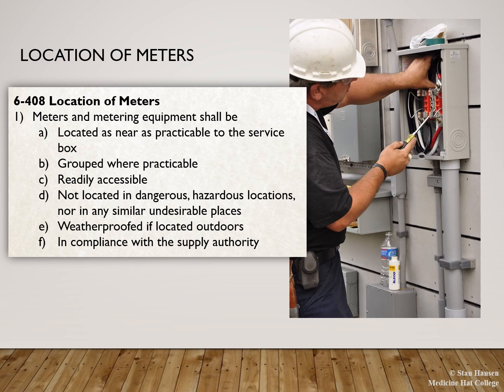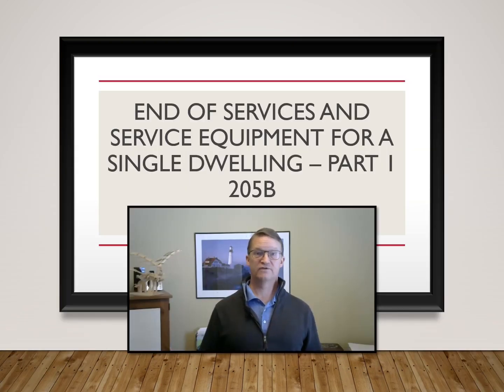When we're thinking about accessibility, we also have to remember Rule 2308, which states that we have to have at least a minimum of 1 meter in front of any of our electrical equipment, and this does include our meter bases. We have to make sure that anybody who's checking on the meter base or working on the meter base has enough level, secure footing to work on it safely. So we can make sure that it's not behind any buildings or structures that's going to impede on that 1 meter rule. So that's the end of 205B Part 1.